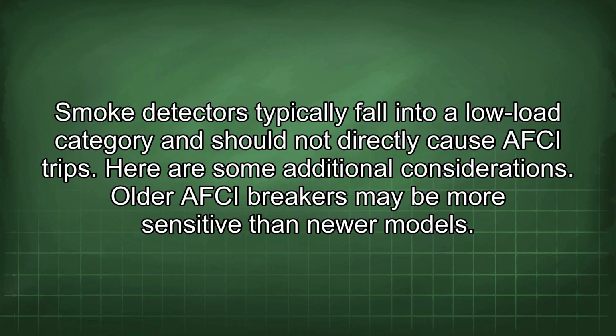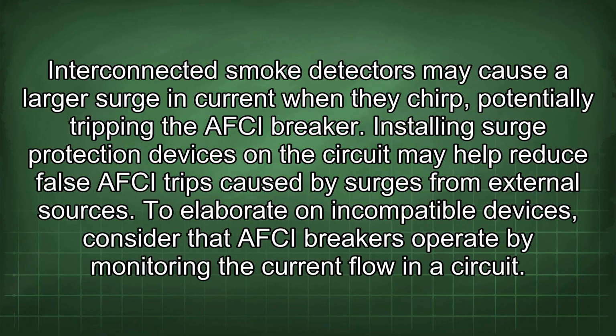Here are some additional considerations. Older AFCI breakers may be more sensitive than newer models. Interconnected smoke detectors may cause a larger surge in current when they chirp, potentially tripping the AFCI breaker. Installing surge protection devices on the circuit may help reduce false AFCI trips caused by surges from external sources.